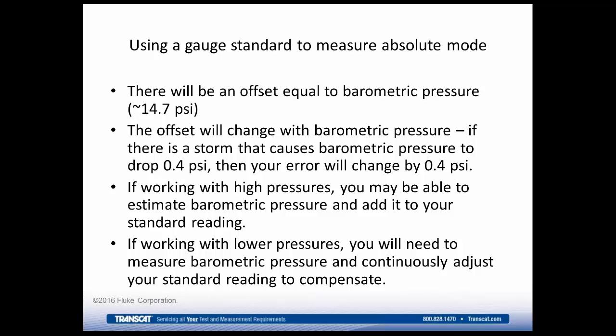With lower pressures, that's not necessarily valid. In those situations, you'll need to measure barometric pressure and continually adjust your standard reading to compensate. So if you have a barometer, then at atmosphere, while your standard is reading 0, your barometer is reading 14.68. So you know, okay, my actual pressure is 14.68. As you go up in pressure, your standard may be reading 1,000, and your barometer is reading 14.7.